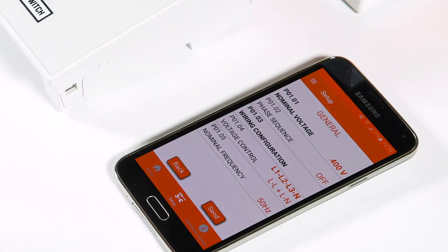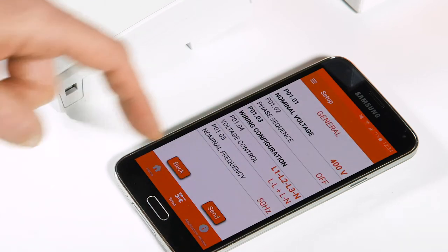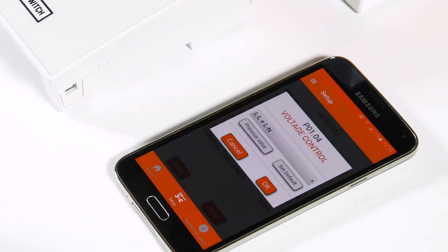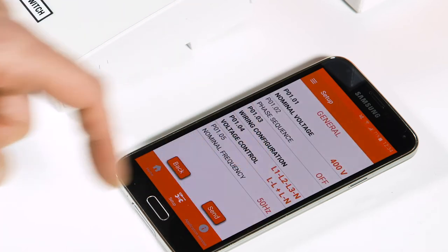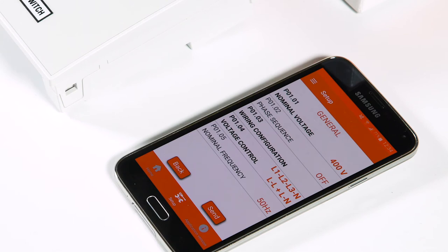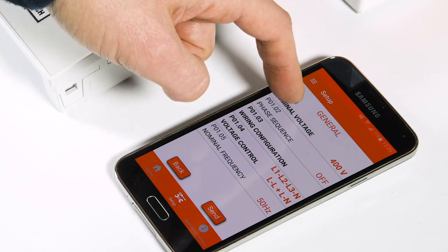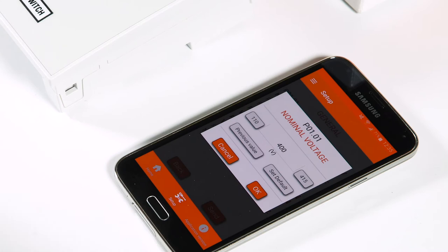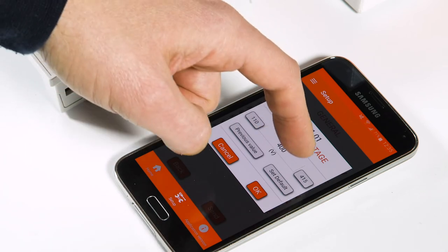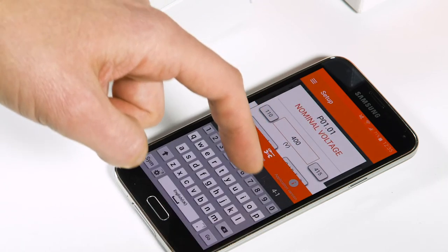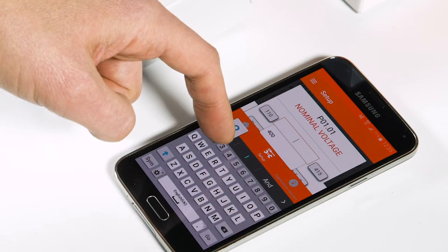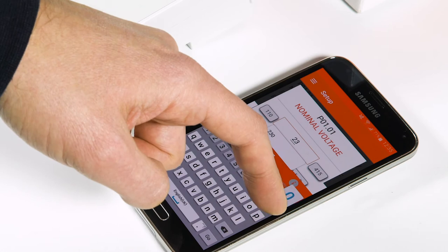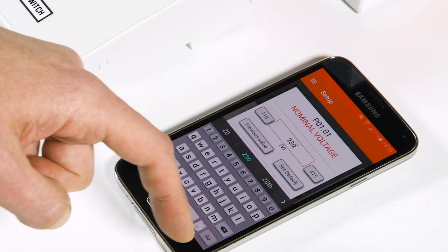Let's see how to change the parameters for a single phase scenario. Press nominal voltage and change the parameter from 400 volts to 230 volts, then confirm with OK. Under connection type, change the parameter to L1N like this.